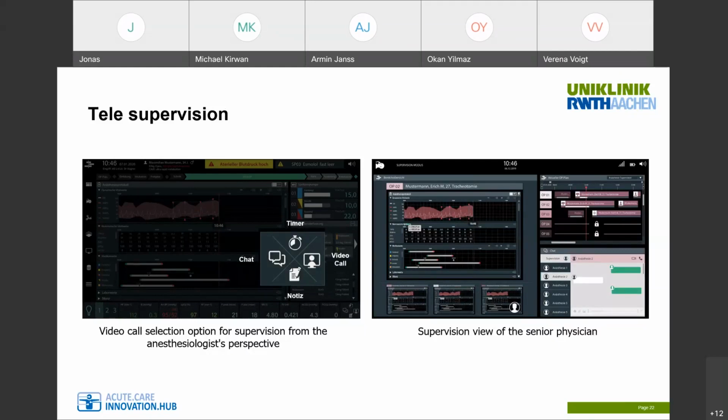Establishing a video transmission with the simultaneous transmission of the data from medical devices that are connected by SDC allows a supervising by a senior physician from a distant site, because the senior physician can get a detailed view of the operating room, not only by video, but also by direct view of the medical devices.